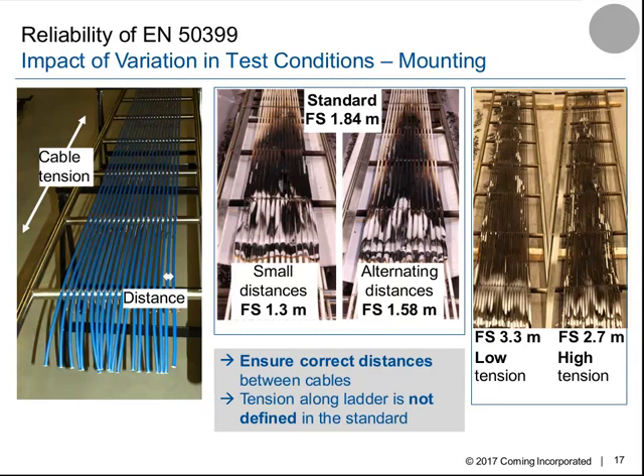The next thing is the cable tension along the ladder. We did this test not with the calibration cable, because the calibration cable is too stiff to apply different tensions. We took a cable where we applied a low and a high tension along the ladder. And what we found is that if we apply a high tension, the flame spread is lowered by approximately 60 centimeter. And this tension along the ladder is not defined in the standard.